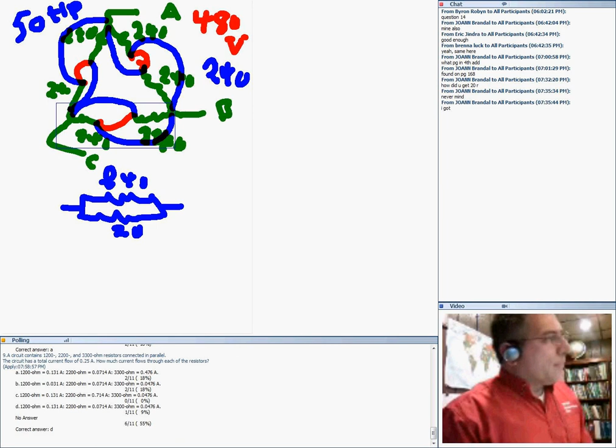Here's what happened: you have a motor like this with 9 leads coming out of it, and the nameplate says 480/240, and they want you to hook up this motor to 240 - hooked up in parallel for 240. If what happens is you grab the leads of this motor that's hooked up for 240 and plug them into a 480 system, you ruin your piece of equipment. That's why with brand new motors, the first thing you need to do is look at the wiring diagram for them and confirm they're dual voltage. You check - is this a 480 motor? Yes. Is it also 240? Yes, now we're good. Is it for 240 only? No, then we have to pay attention to it.